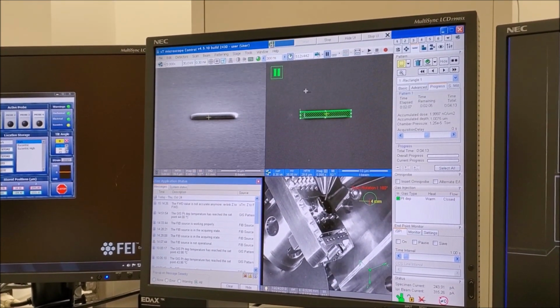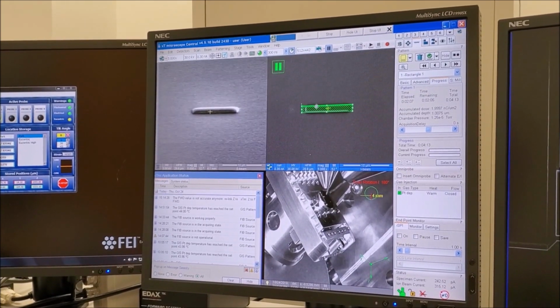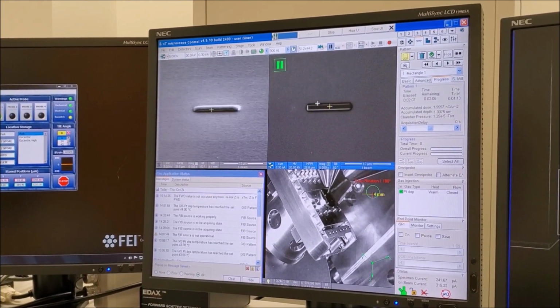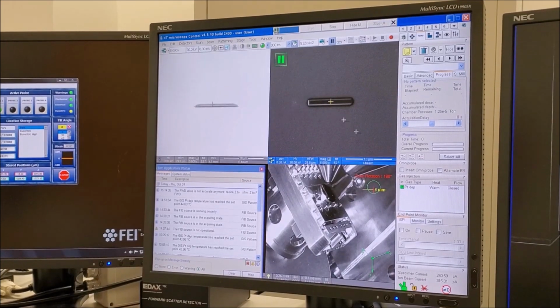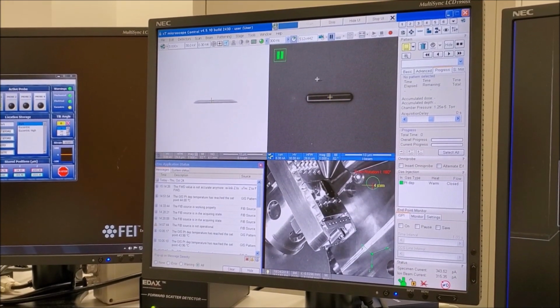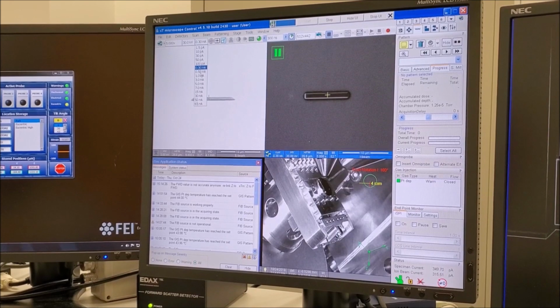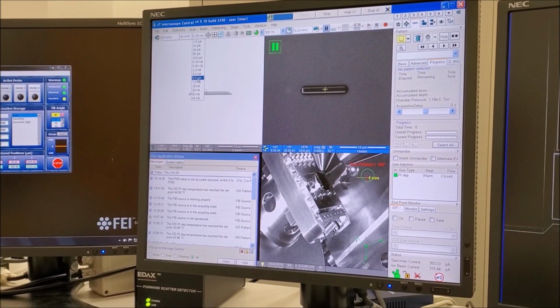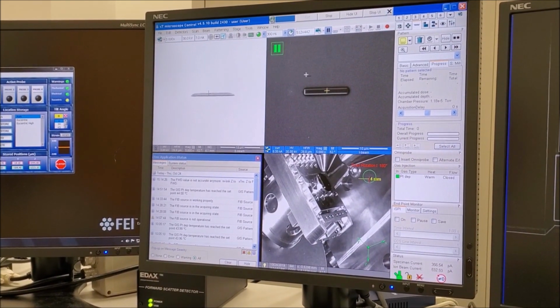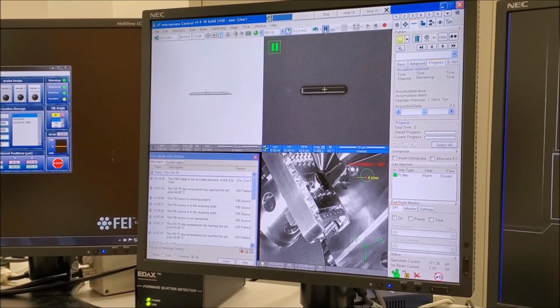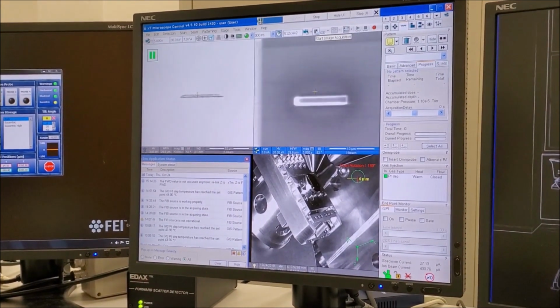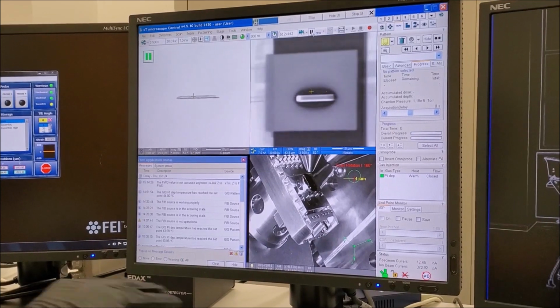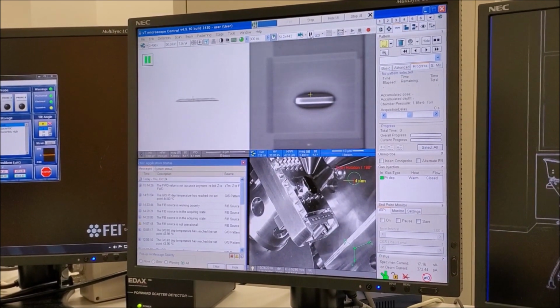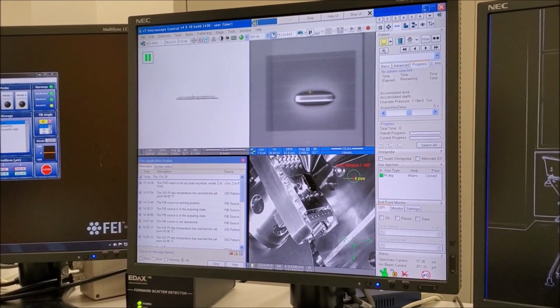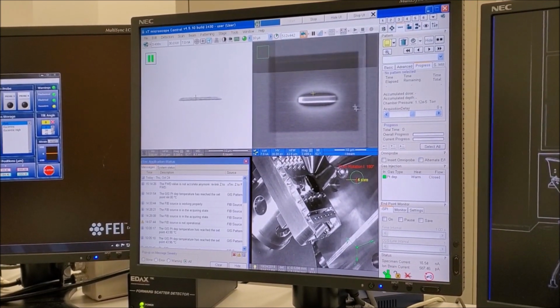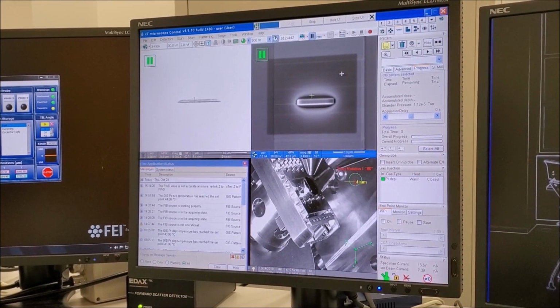Select and delete any patterns that may be present in the ion beam quad. Then select an ion beam current to be used for cross-sectioning, which is typically in the nanoamp to tens of nanoamp range. Unpause the ion beam image, perform auto contrast and brightness, and use the focus knob on the manual user interface to focus. Do this as quickly as possible so as to minimize the time spent live ion beam imaging.